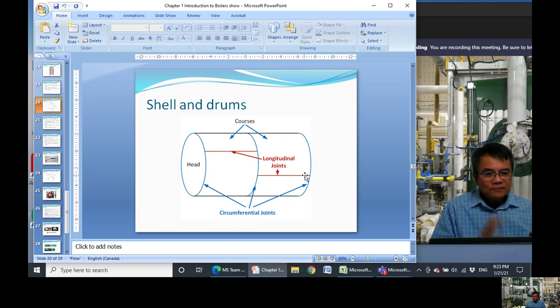Now, and when it fails, usually this one is the first one that fails. Now, probably only around 10, 15 years ago, they had a really big accident in one of the teaching colleges, BCIT, a really big college too. One of their fire tube boilers exploded, because, you know, just like us, they start the boiler, cool it down, start, cool it down.